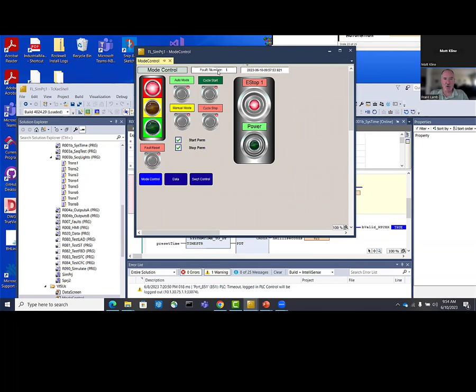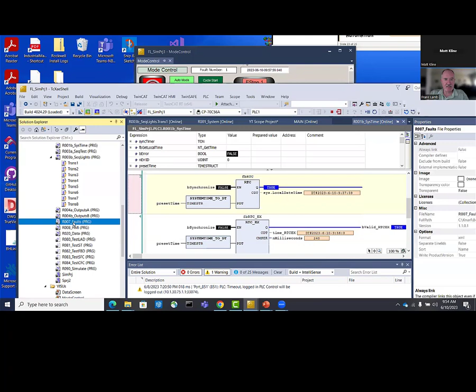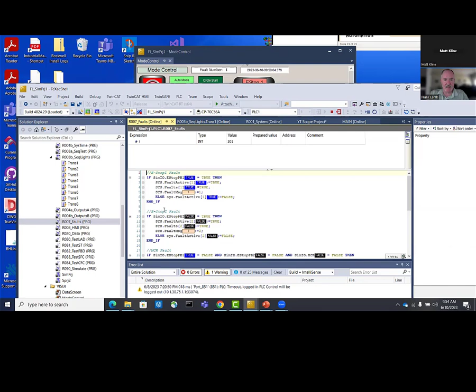I just hit the E-stop. What did that do? It took me out of auto cycle. It put me into a fault. It told me the fault number, which comes from one of these routines down here. Faults, there's a little bit of that logic. So I'm monitoring things. It says, okay, you have an E-stop 1 fault. If so, your system fault message is 1. Now I'm going to reset the E-stop. Okay, I fixed that. Now I have fault number 3. That is the MCR is not active.